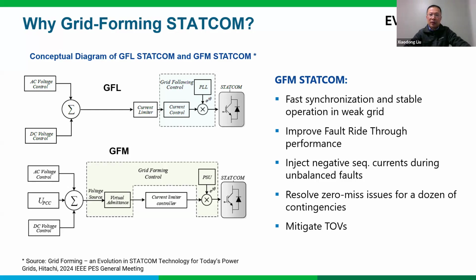Another advantage of the grid forming STATCOM is that it produces a good amount of negative sequence current, right? So especially on the unbalanced fault, right? This helps the protection to recognize the fault type and locate the fault. More importantly, it also helps to resolve the zero miss issues for a dozen of contingencies in South Fork Wind. Additionally, this voltage source behavior has been found to be useful to mitigate the TOVs, that is the temporary overvoltages. All these distinct features of grid forming control help the South Fork Wind successfully integrating into a very weak grid.